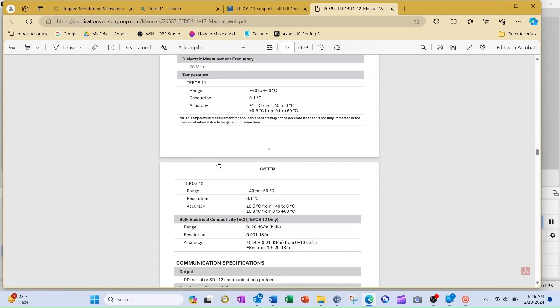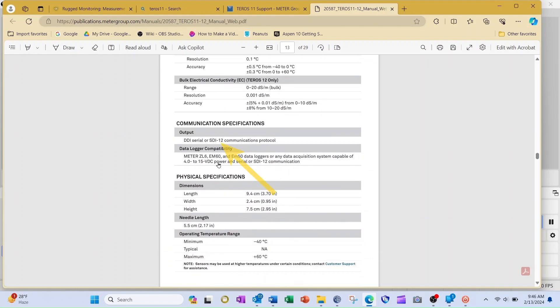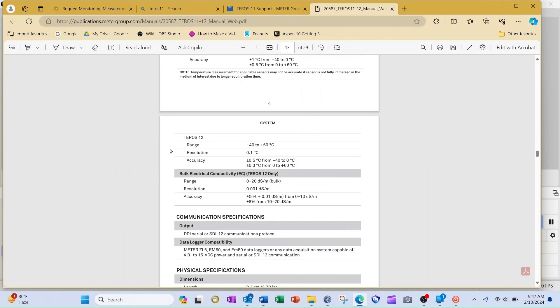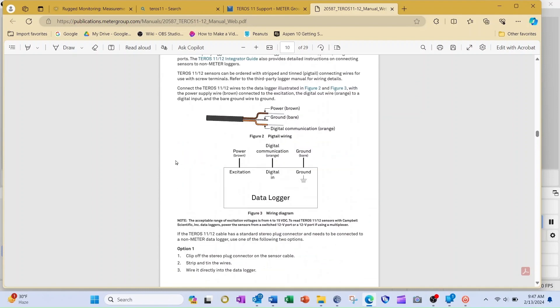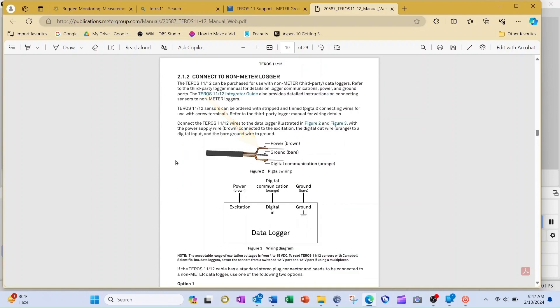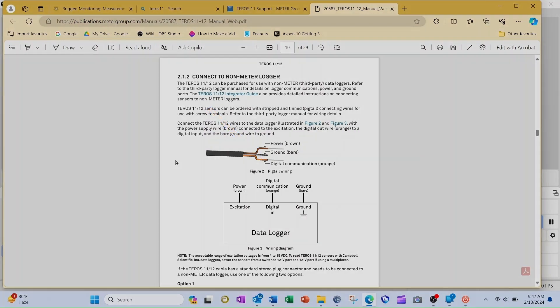In this case, the user manual for the TEROS 11 gives the output is SDI 12, and that the brown wire is power, the bare wire is power ground, and the orange wire is digital communication. That's what I need to know to finish my wiring diagram.